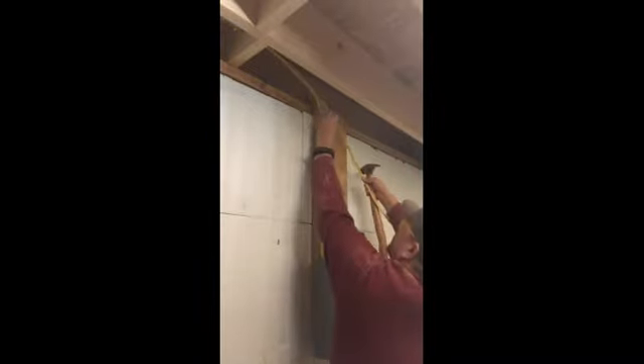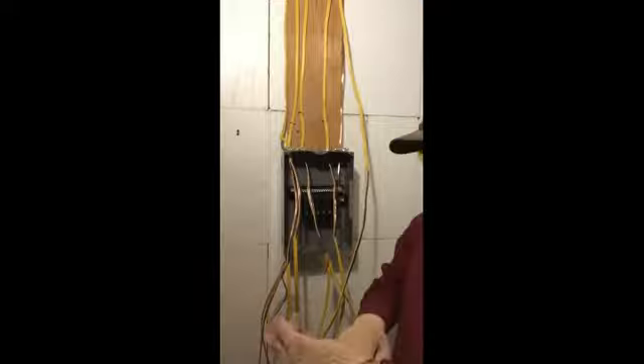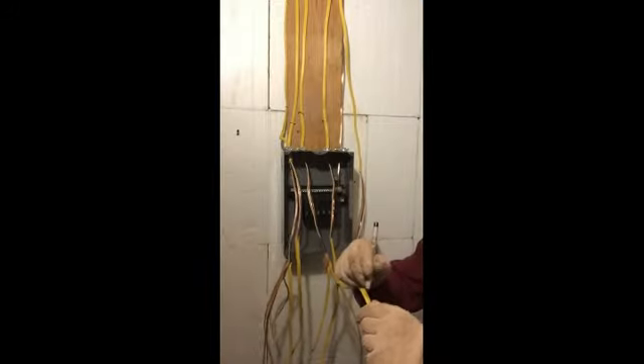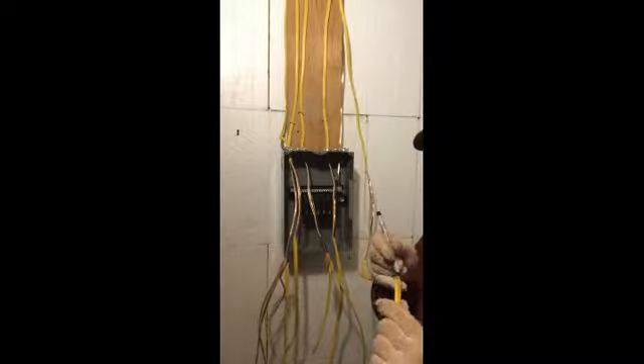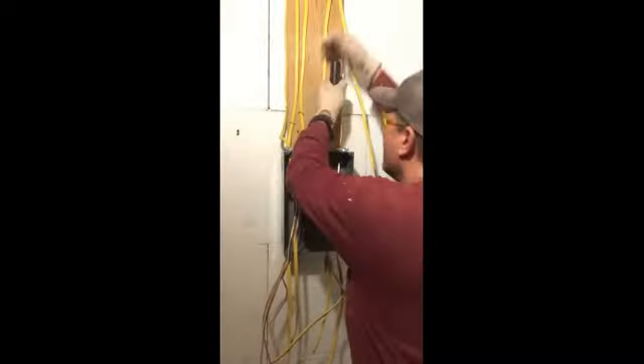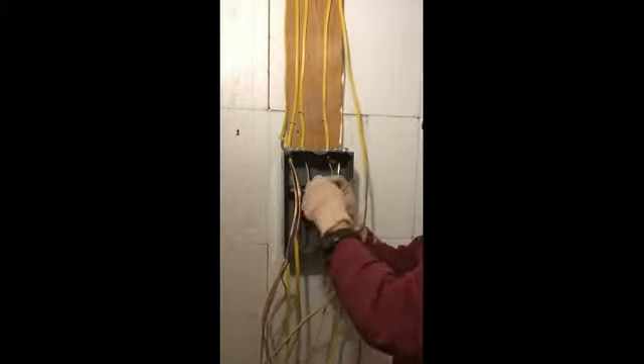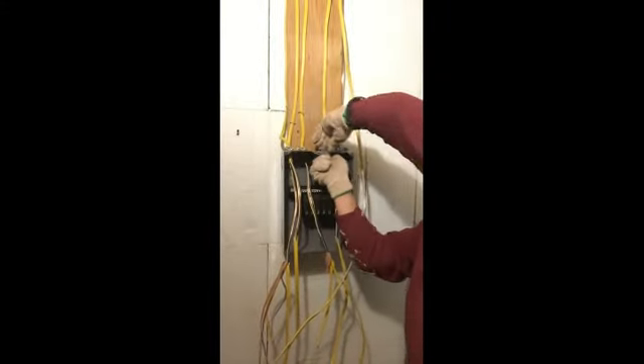Step 9, panel box wiring. I'll go to the corner of the basement where you'll see an array of number 12 wires dangling down to the floor. You will secure a piece of OSB plywood to the wall and secure the 4 corners of the panel box, in this case a 200 amp panel box, to the OSB, which is secured to the wall. It's best when you're running circuits that you leave about 4 times the length, because you might need to wrap it around the inside of the panel box of these wires. So make sure you leave about 4 times the length when you cut them.